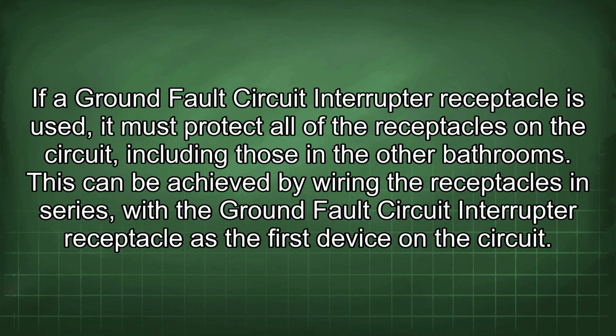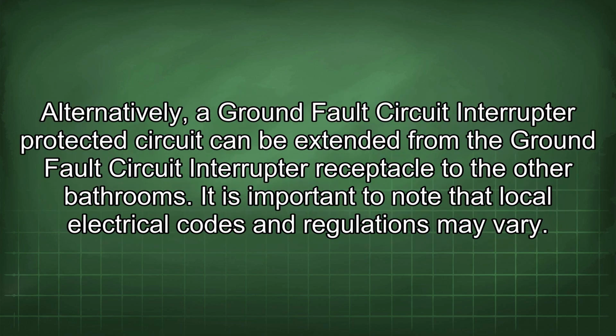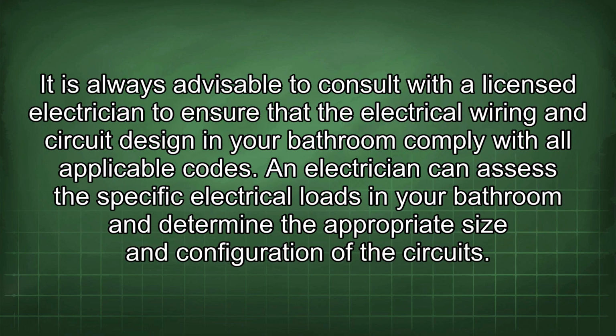This can be achieved by wiring the receptacles in series, with the ground fault circuit interrupter receptacle as the first device on the circuit. Alternatively, a ground fault circuit interrupter protected circuit can be extended from the ground fault circuit interrupter receptacle to the other bathrooms. It is important to note that local electrical codes and regulations may vary. It is always advisable to consult with a licensed electrician to ensure that the electrical wiring and circuit design in your bathroom comply with all applicable codes.